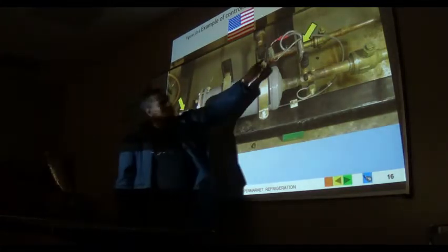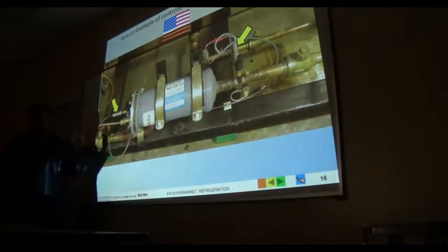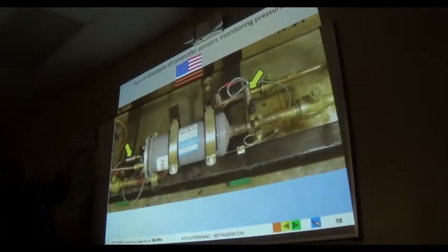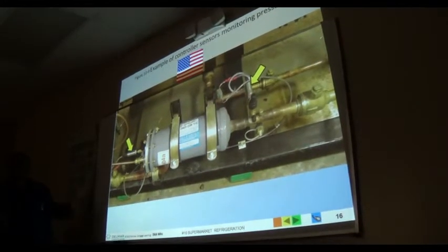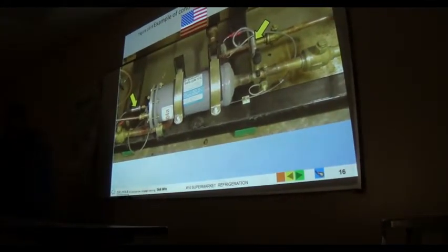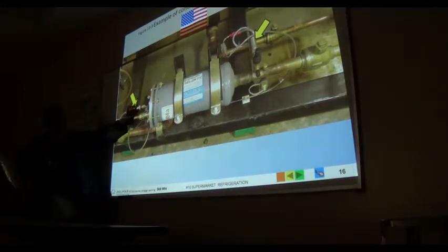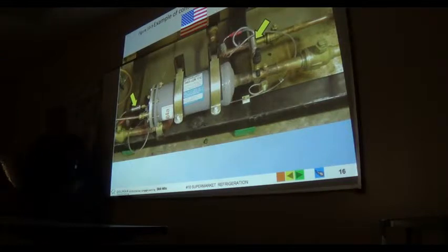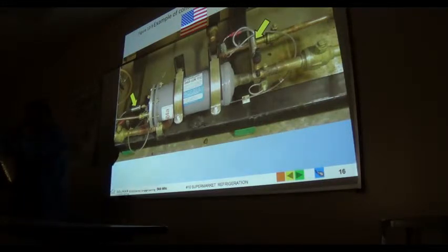See, these are all either pressure transducers or the NTC or PTC. And these are all going to go right into your controller board, and whatever input, that's going to sense it here. How do you know which is which? This is pressure. No, but how do you know which one's the positive? We will not know which one is positive or negative. What they do, they have controllers with sensors that are specific to the system. And this cable is a gray cable. If it's a specific manufacturer, they may have this manufactured with a yellow sheath, meaning that's theirs. The only way I can tell if it's an NTC or PTC is to put the meter on it and check resistance as I vary the temperature.